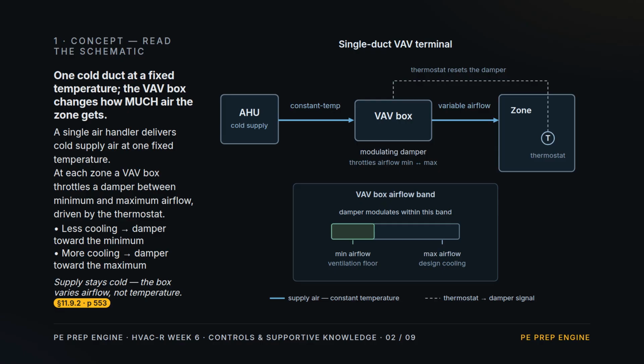Concept 1. Read the schematic. On the left, a single air handler delivers cold supply air at one temperature. That supply temperature never changes. At the zone, a VAV box throttles a modulating damper between a minimum and a maximum airflow, and the space thermostat, marked T, drives it. When the zone needs less cooling, the damper closes toward the minimum. When it needs more, it opens toward the maximum. Notice the airflow band at the bottom. The box rides between a minimum set by the ventilation floor and a maximum set by the design cooling load.